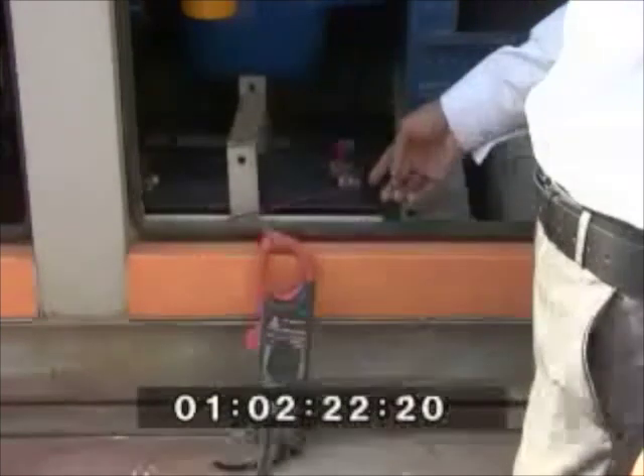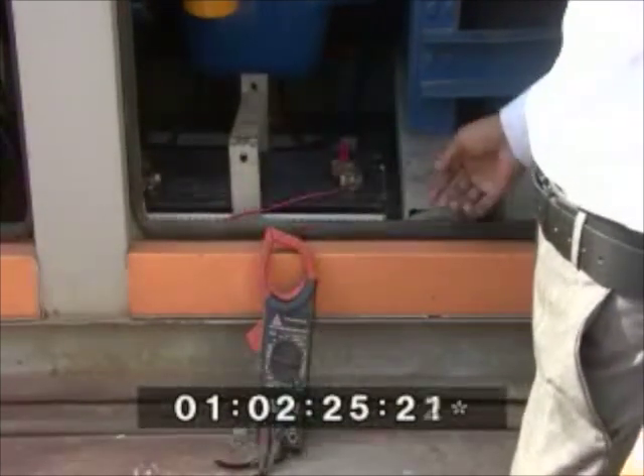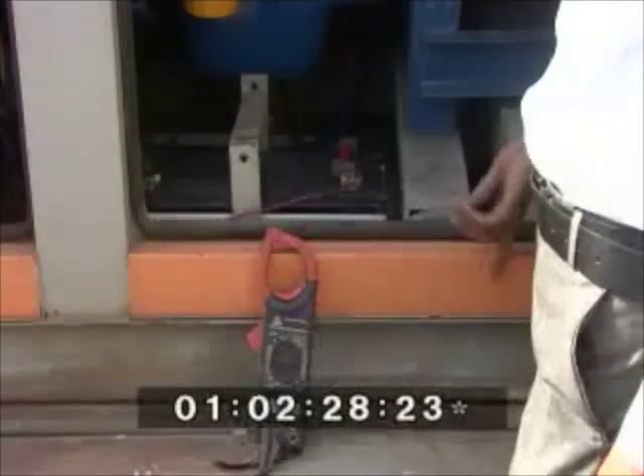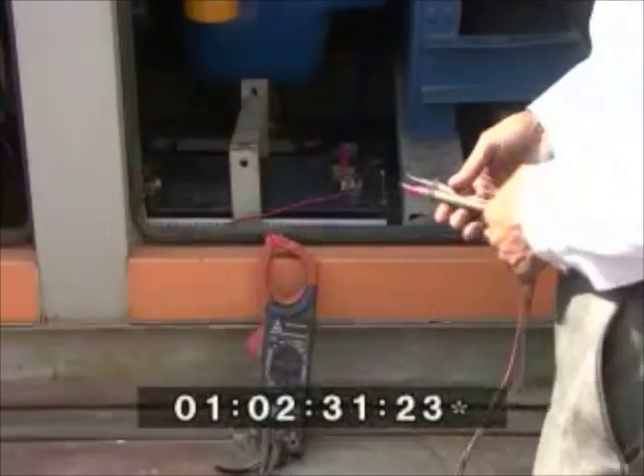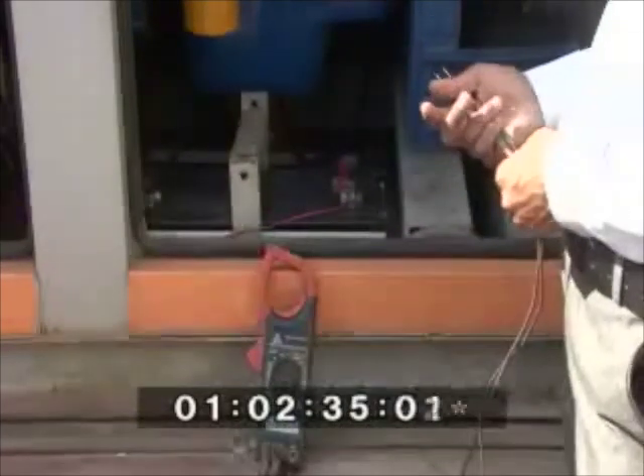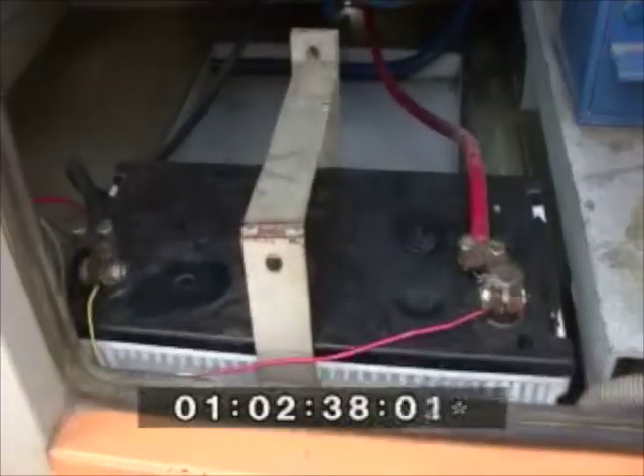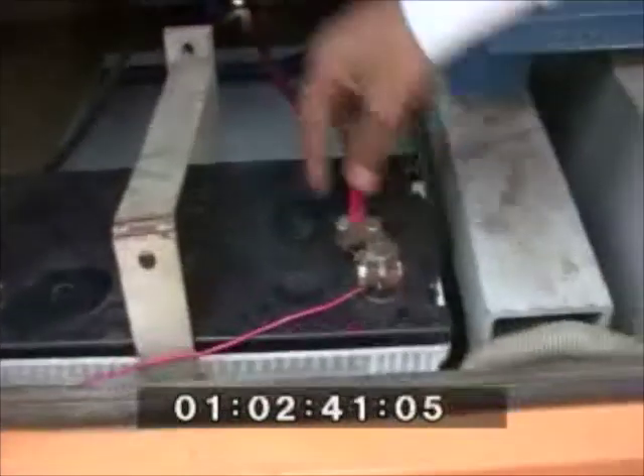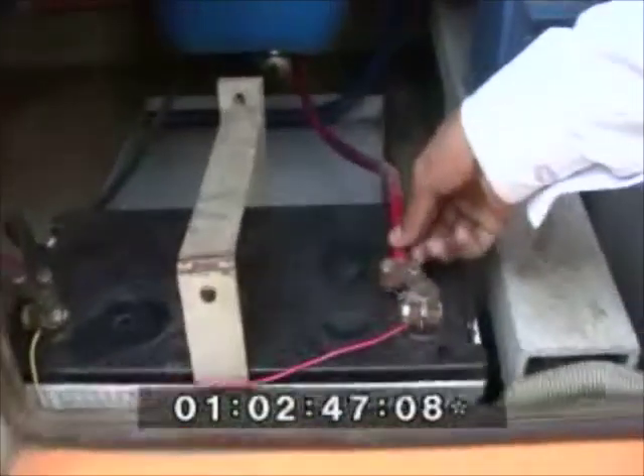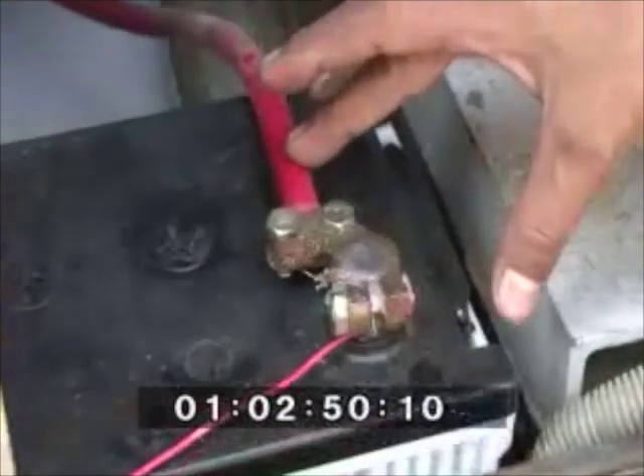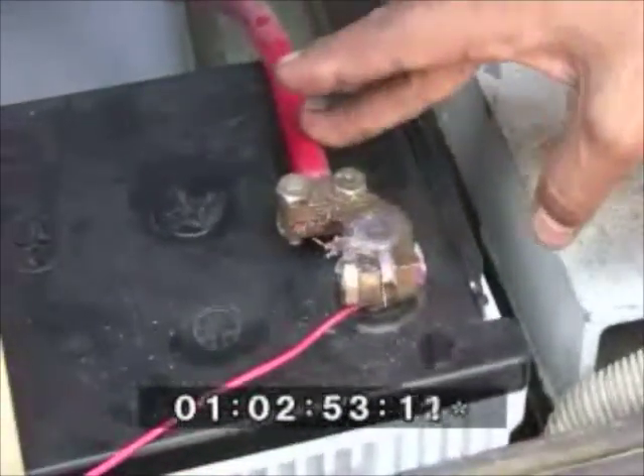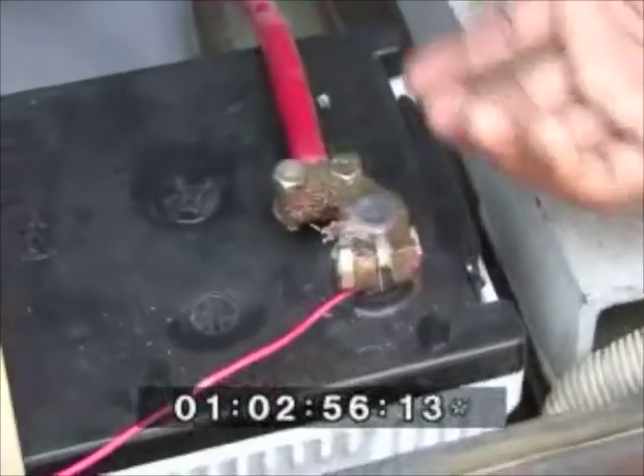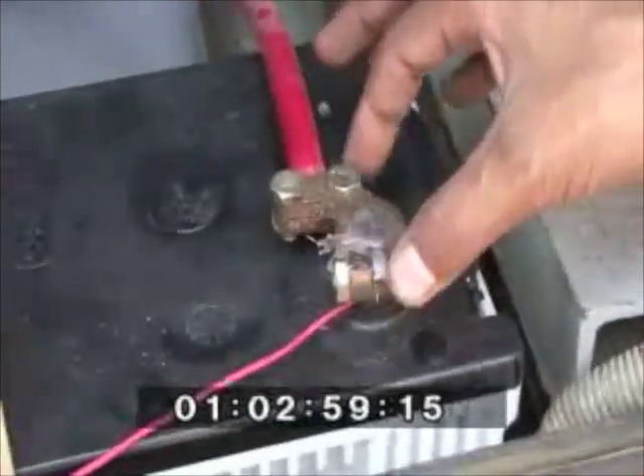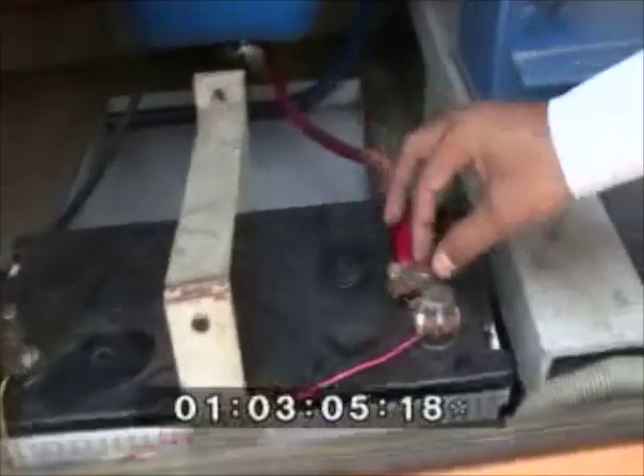Now we will look for the tightness in the connectors of the battery. There are two terminals in the battery, positive and negative. The red one is positive and the black one is negative. Both the terminals should be tight. Loose terminals may lead to break of wire, sparking of connectors, low battery charging, and leading to starting problems of DG on auto mode.